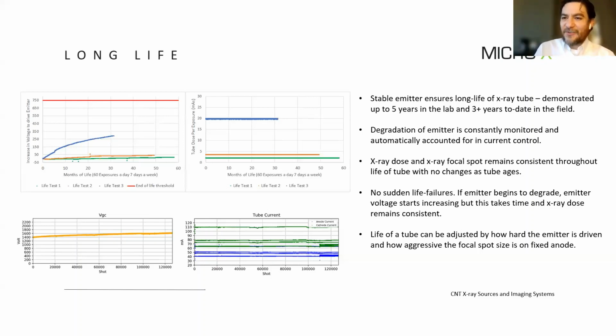But even as it degrades, you still get highly consistent imaging. And if it was to suddenly start degrading rapidly, even then it's not a binary ending. It's not like a filament that bursts. As the emitter begins to degrade, the voltage to drive it goes up, but it's going up steadily. It's not an instantaneous death because of all that built-in redundancy. So we're able to see when a tube is likely to die and be able to replace it, as opposed to just being an instantaneous death.